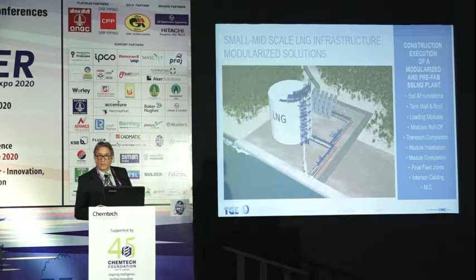All the modules have been then shop fabricated and tested beforehand, so that there is then needed only a minimum of field construction. There will be some site field joints which are minimized, so welding connections that need to be tested certainly. And what also has to be done on site is the cable pulling interconnection, whereas the modules itself are already fully cabled.